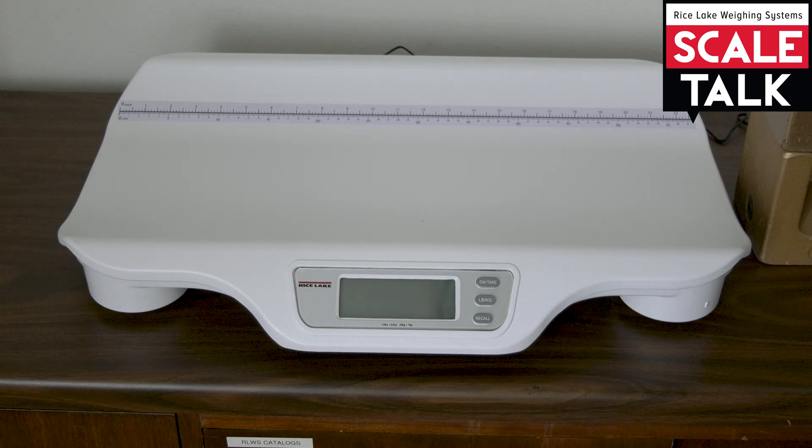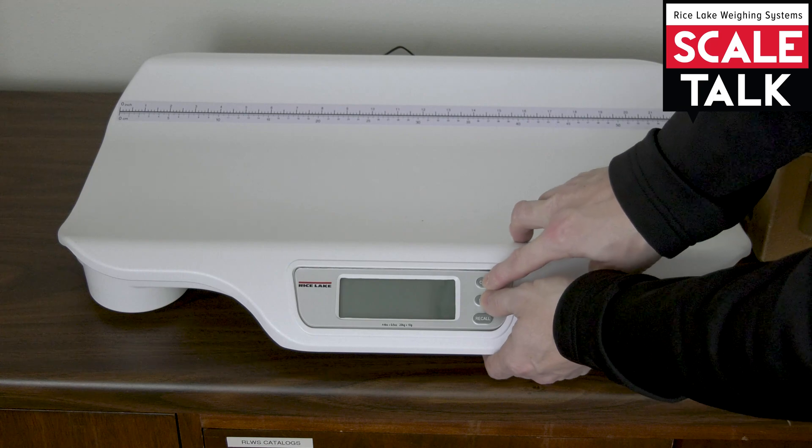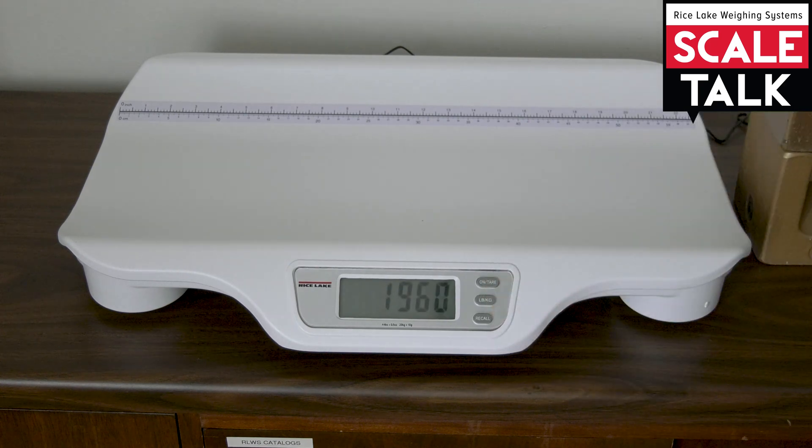To get into calibration mode we're going to press and hold the on-tare and pound-kilogram keys until we see raw counts on the display.